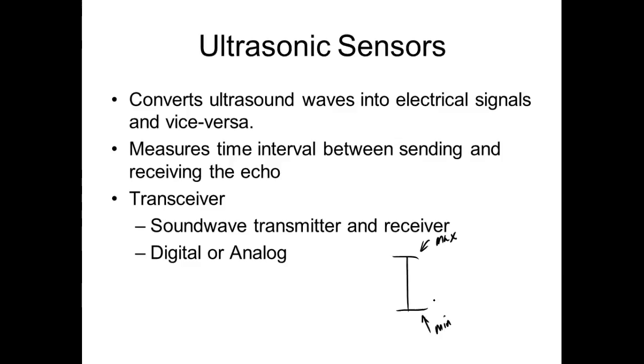Of course, we have to set it up for a reference. What we do on that one is we have two blocks over there. One of them is the maximum height, and we put that under the ultrasonic sensor, and it's got a big U on the top for the upper limit. The other one has a big L on top of it for the lower limit.